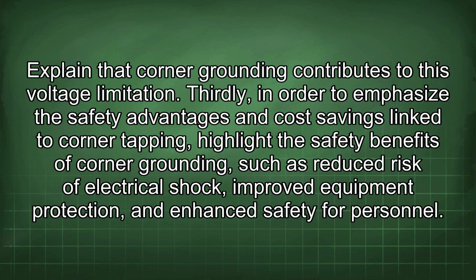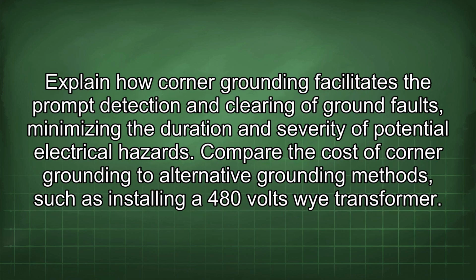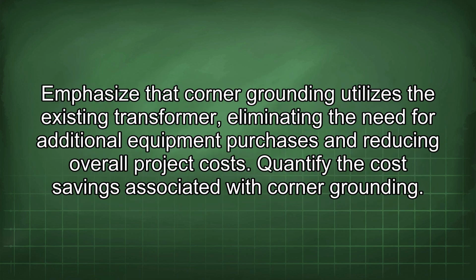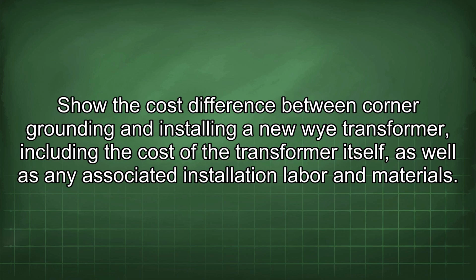Thirdly, in order to emphasize the safety advantages and cost savings linked to corner tapping, highlight the safety benefits of corner grounding, such as reduced risk of electrical shock, improved equipment protection, and enhanced safety for personnel. Explain how corner grounding facilitates the prompt detection and clearing of ground faults, minimizing the duration and severity of potential electrical hazards. Compare the cost of corner grounding to alternative grounding methods, such as installing a 480-volt wye transformer. Emphasize that corner grounding utilizes the existing transformer, eliminating the need for additional equipment purchases and reducing overall project costs. Quantify the cost savings associated with corner grounding. Share the cost difference between corner grounding and installing a new wye transformer, including the cost of the transformer itself, as well as any associated installation labor and materials.